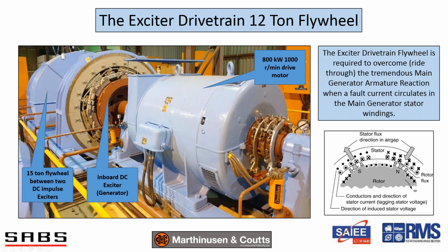Now, what happens to the generators? The current that they produce is importantly linked to their speed, and if they are loaded substantially and their speed drops, then the excitation, the armature output, in other words the field current into the generators, will be reduced. This is all related to what is called armature reaction, where, when current is set up in the stator, it will oppose the current in the field as well. So you basically have to have a very powerful supply to overcome the armature reaction from the stator fault current affecting the rotor. So that's the reason for the flywheel.